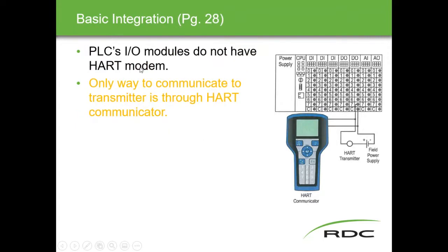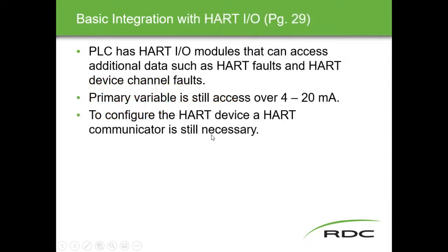Okay, basic integration. What does that mean? It means that the PLC's IO modules do not have a HART modem. Basically, if I had an analog input card or an analog output card, and it's not got the HART brand on it somewhere, it's just a regular analog input card and it will offer you nothing beneficial from a HART transmitter. You need to have the HART modem, either as a handheld device or built into the card, in order to communicate with a HART device.